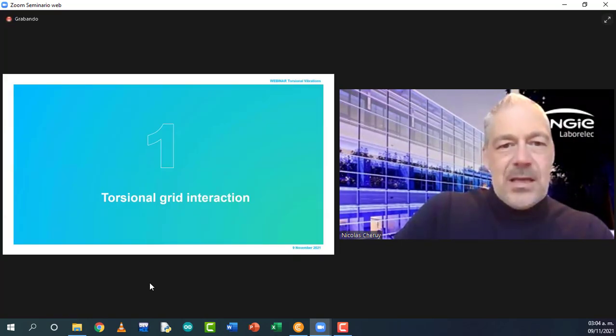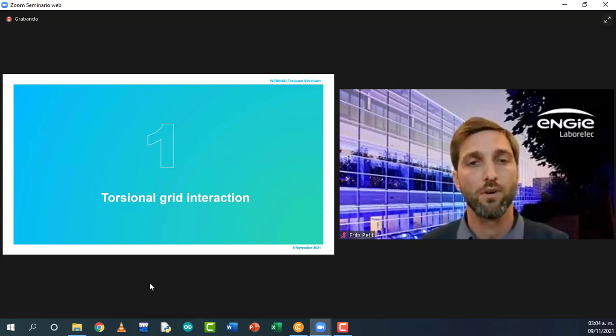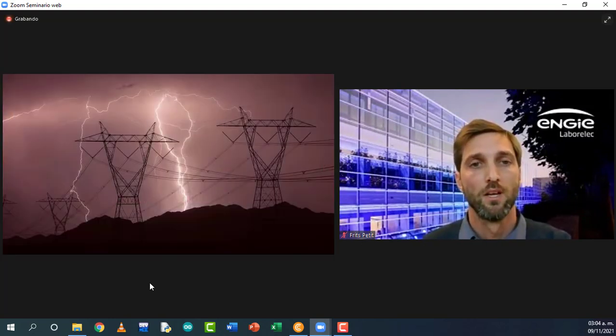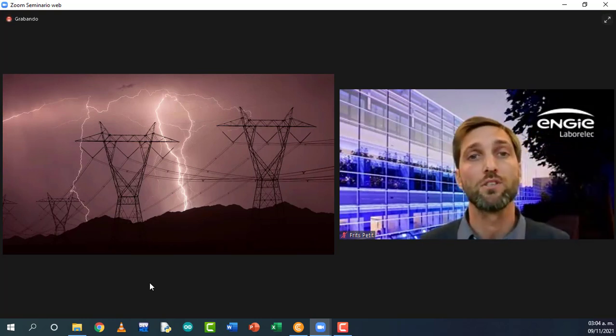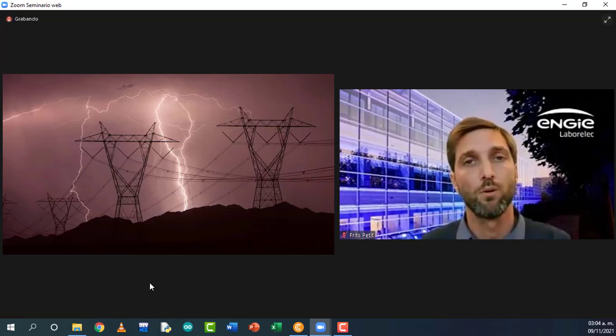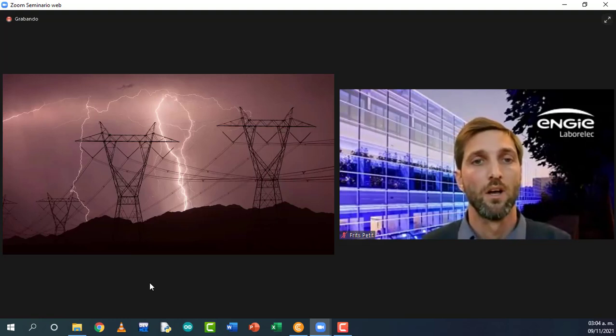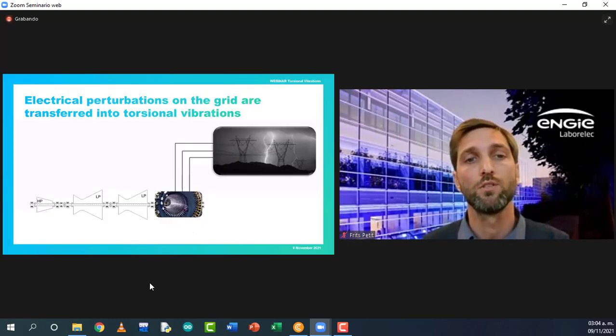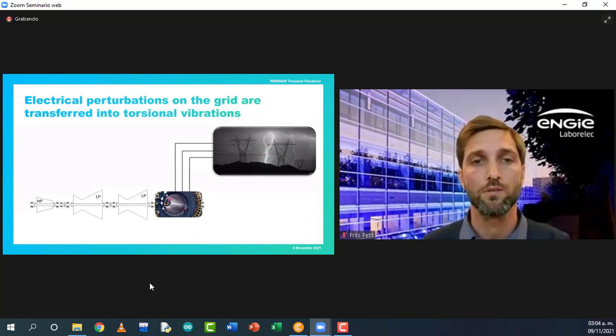Thanks, Nicolas. So let's now get started with the first part, the torsional grid interaction. The lightning strike, I think we're all aware of the potential impact it can have. But did you know that it can also have an impact on your turbo generator shaft line? How is this possible? Well, your turbo generator shaft line is of course connected to the grid by means of the generator. So every perturbation on the electrical side will be transferred by the generator onto the mechanical side. This also holds for the lightning strike.